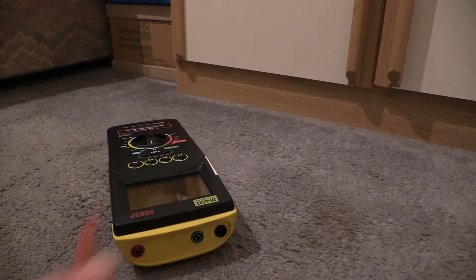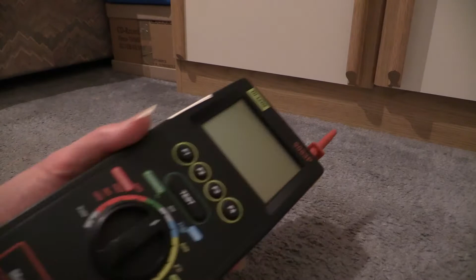And in that black one, you'd connect another probe, so you then push the whole test unit into wherever you're going to test, and the other test probe, which would be on a lead, you push that in. Between the black probe and the red one, you'll be measuring a voltage or something - quite possibly voltage. That's the idea of the little stumpy probe, so you can connect that in and use the whole unit as a test probe. So yes, that is what that is for.